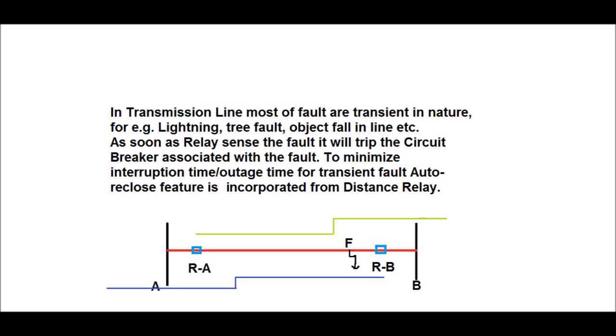In transmission lines, most of the faults are transient in nature, for example lightning, tree fault, object falling on the line, flashover of insulator, etc. As soon as the relay senses the fault, it will trip the circuit breaker associated with the fault. To minimize the interruption time or outage time, an autoreclose feature is incorporated in the distance relay.